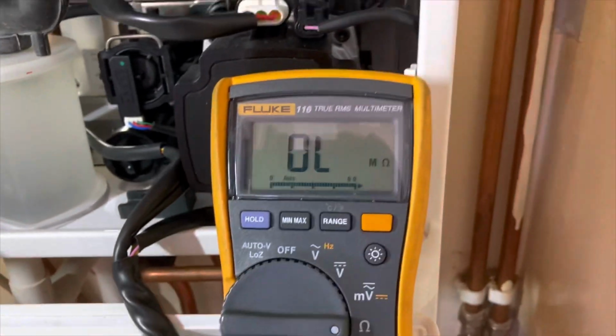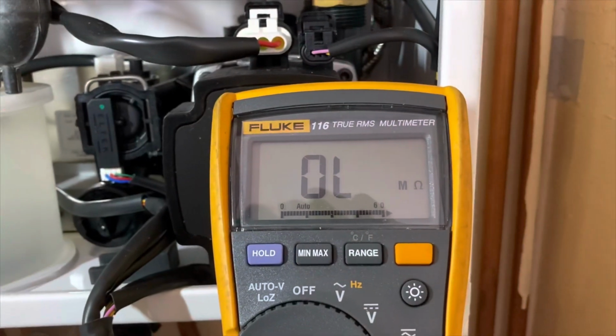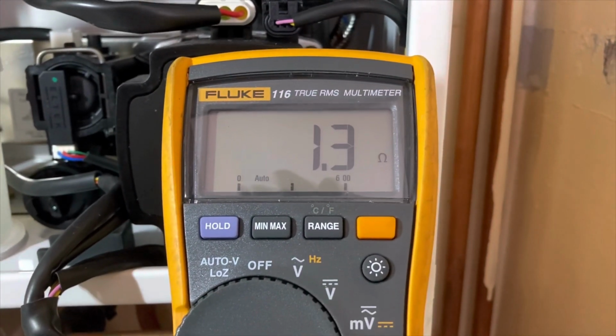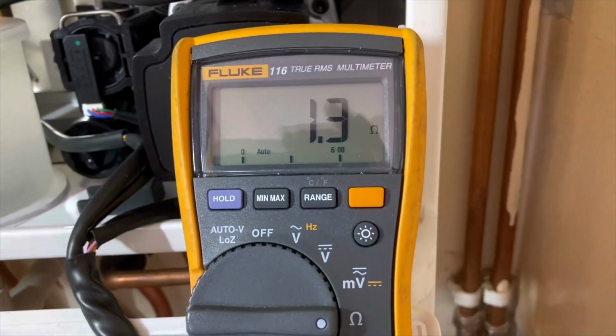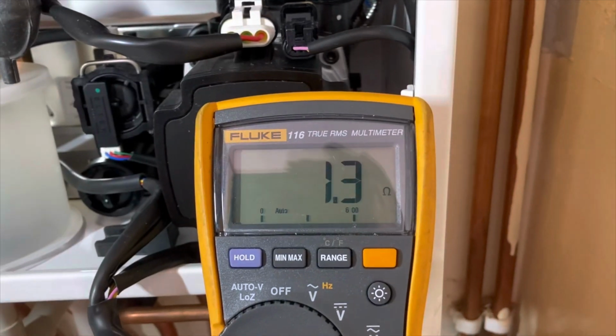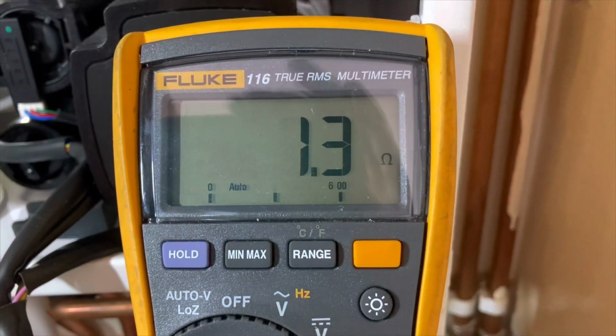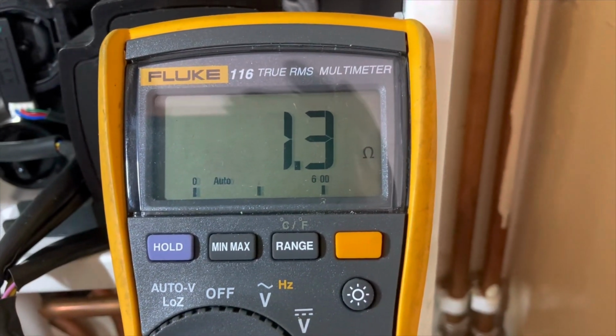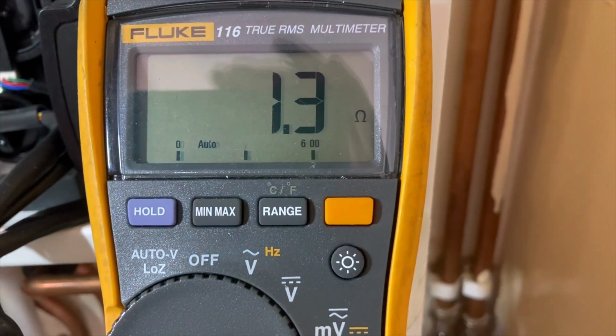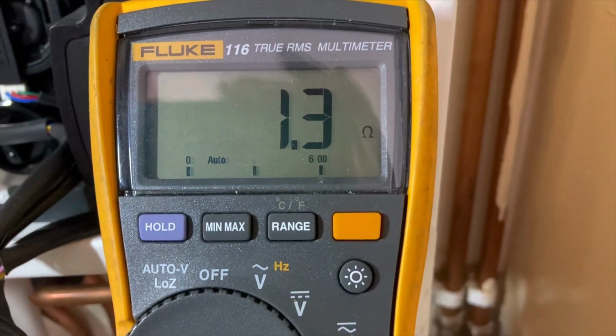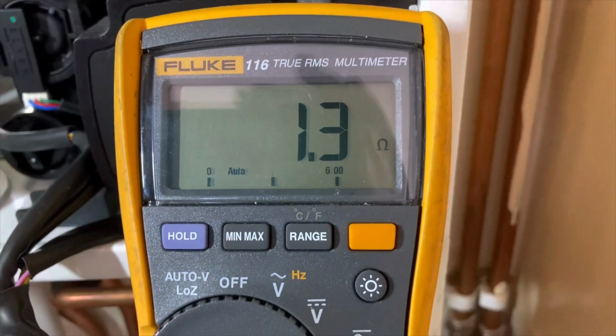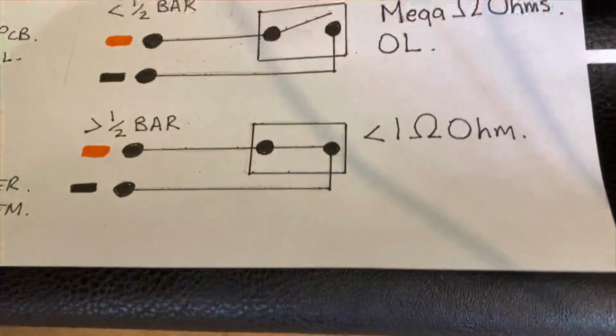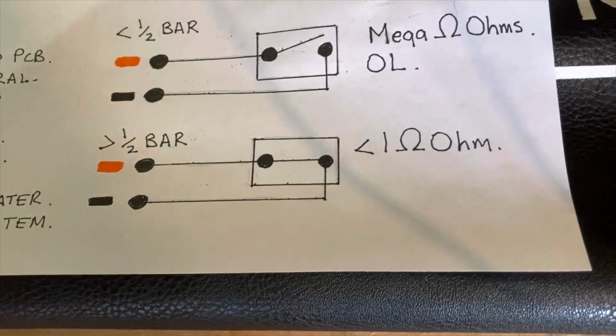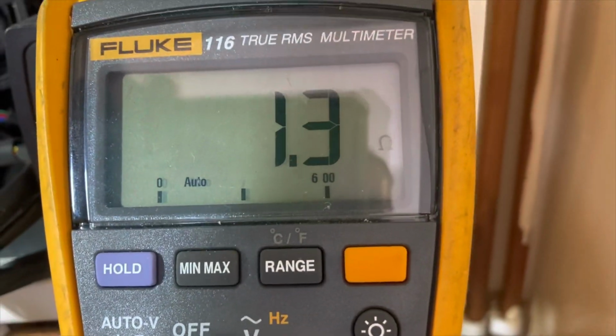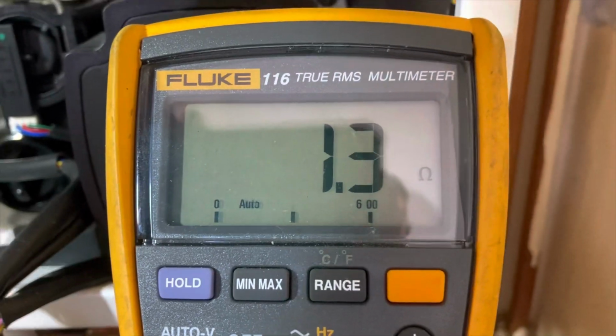What I'm going to do, I'm going to try to do this with one hand. I'm going to put some pressure in the boiler, and there you go. You may have heard the click as well. You saw my multimeter change to 1.3 ohms. It's saying 1.3 because my leads test about half an ohm. When you test them together, you'll get a bit of resistance through there. So if you take off the 0.5, you'll get like 0.8. So that's less than 1 ohm, which we said we'll get. Greater than half a bar, you get between 0 and 1 ohm, and that's what we're reading there. I just topped up the pressure. You heard the click. That's how you test that switch. It's as simple as that.